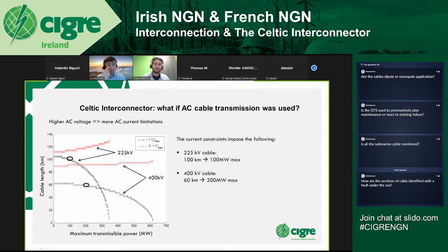The current constraints, shown in the black curves, impose the most limitations on power system transmission. For a 225 kilovolt cable, if we have a 100 kilometer cable, the maximum transmissible power will be 100 megawatts. For a 400 kilovolt cable, for a 60 kilometer cable, the maximum transmissible power will be 200 megawatts.